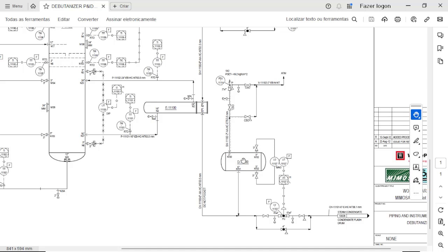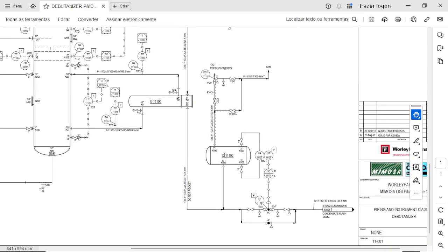And to keep the balance in this reboiler, we have a condensate pot that is responsible for calibrating or equalizing the pressure in the system. This condensate pot has a control loop associated with a control valve that is shown as an LV, an LIC, a transmitter for level transmission, and we have an LG, which means in the field, in the local position, we have a glass where it is possible to see the level of this equipment.